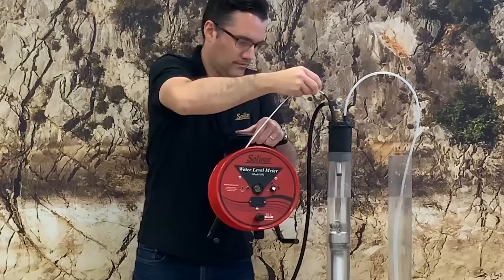Currently, the best-selling version of the Model 101 is the P7 water level meter. It is ideal for a vast majority of water level monitoring applications, including boreholes, wells, standpipes, and tanks. The Model 101 features the P7 probe, completely submersible to the full length of the tape, which can span up to 1,500 meters or 5,000 feet. The P7 probe accurately and consistently measures water level with almost zero displacement due to the sensor location at the tip of the probe, and can even be used to confirm total well depth because it is pressure-proof.